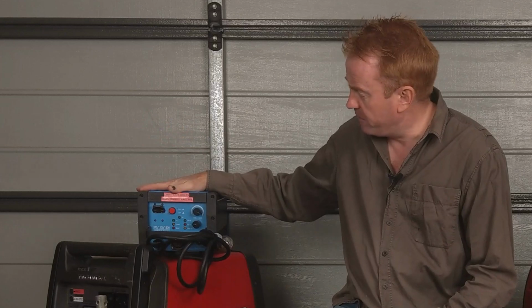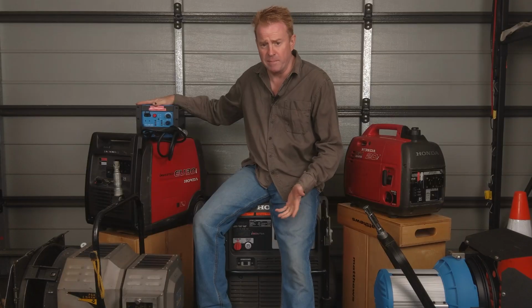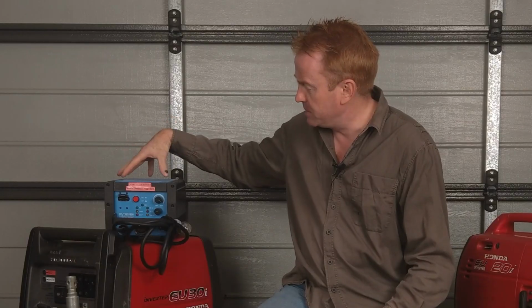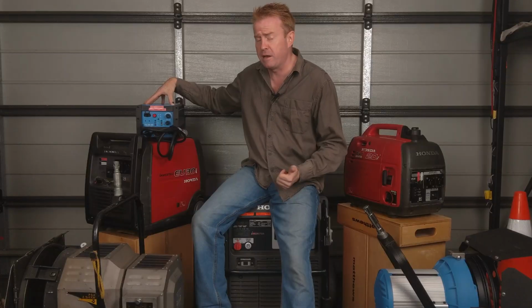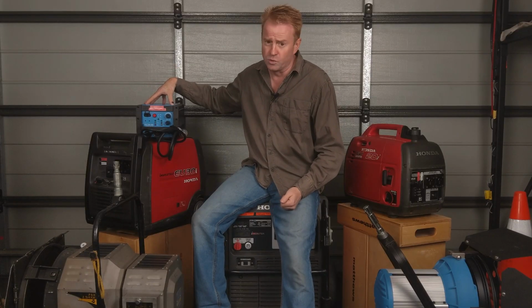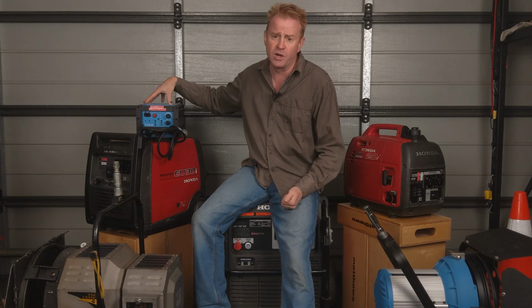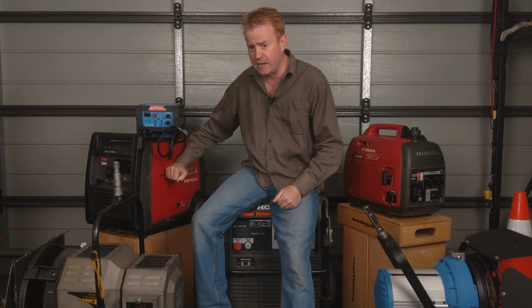Now, if you have a power factor corrected ballast, you can run an M18 off a 3 kVA generator, no problem at all. To give you some idea of the difference between power factor corrected and non-power factor corrected ballasts, this ballast here is 10 years newer technology, plus it's power factor corrected. It actually draws over 900 watt less power than the other ballast. 900 watt less. That's a lot on a 3 kVA generator.